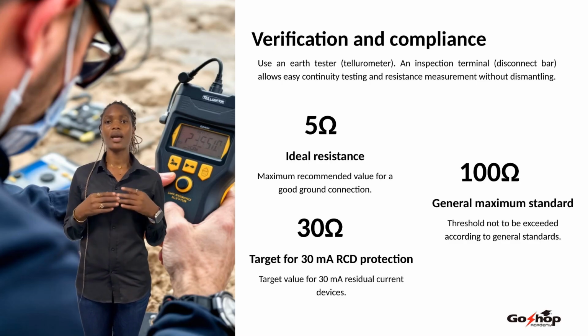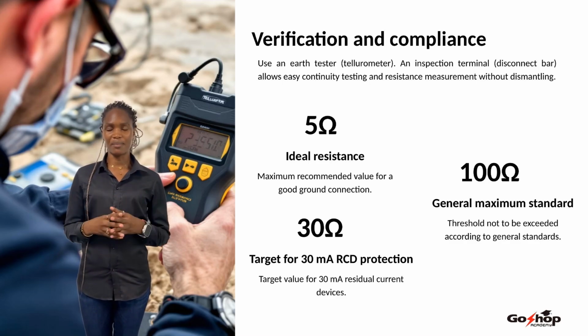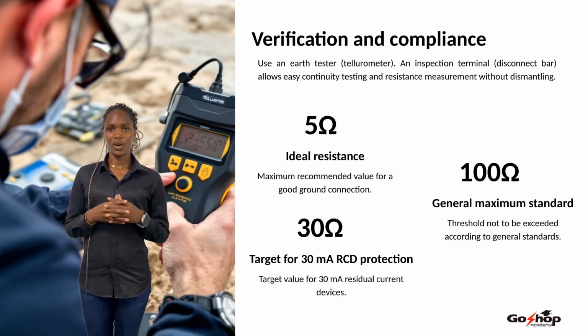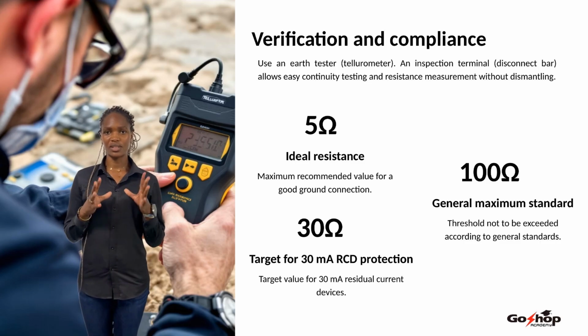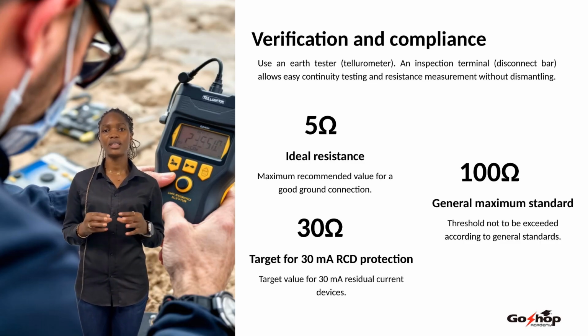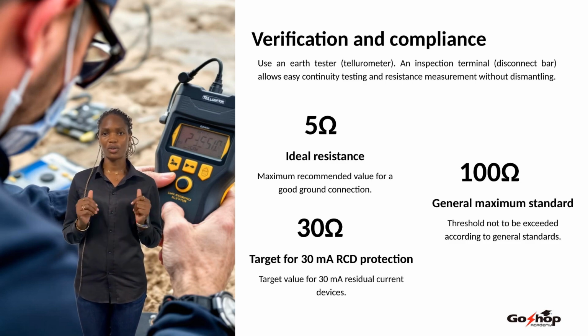5 ohms, ideal resistance, recommended maximum for good grounding. 100 ohms, general limit according to standards. 30 ohms, target value for 30 mA RCDs to ensure optimal protection.